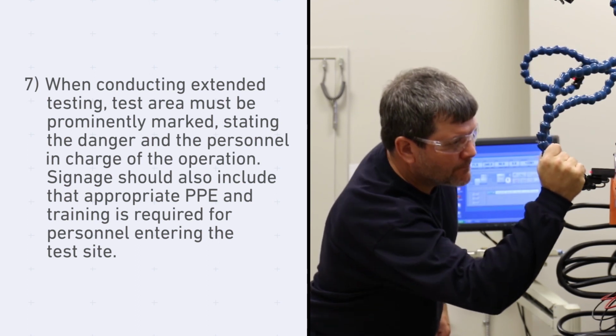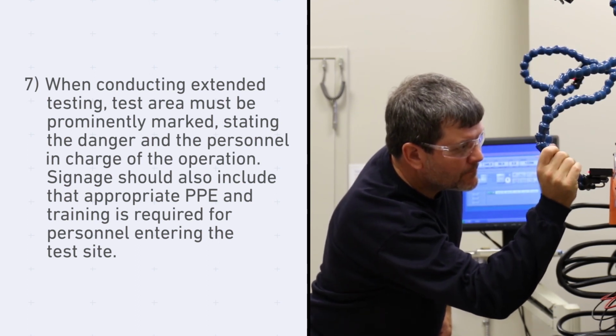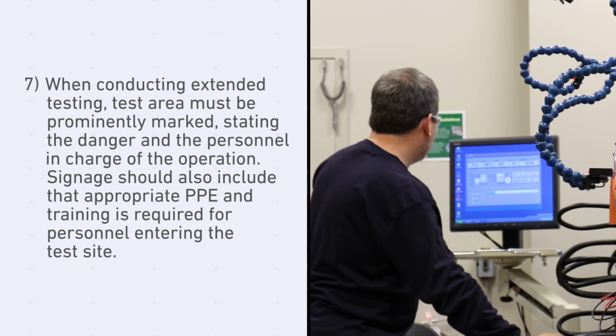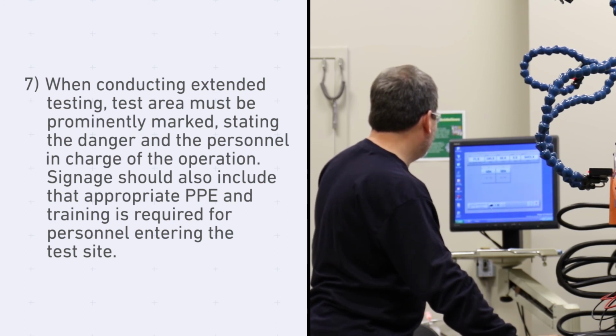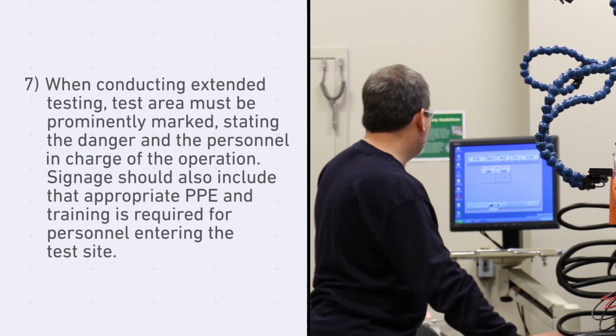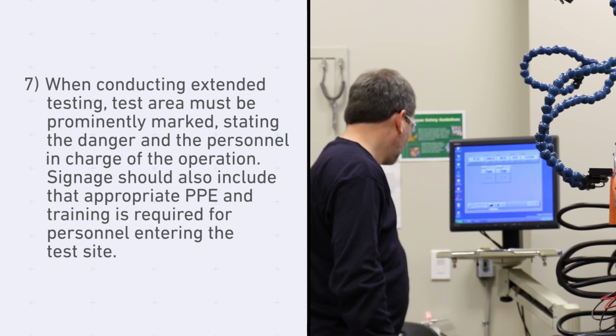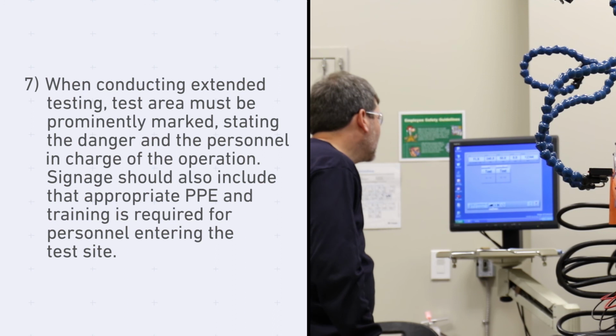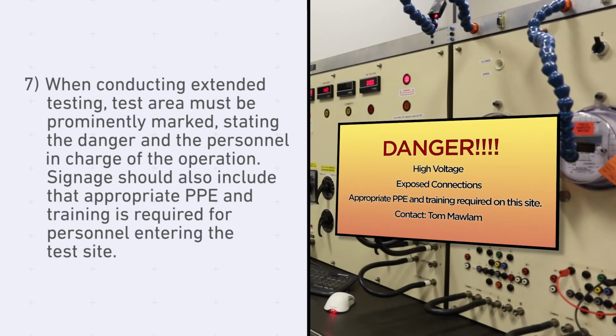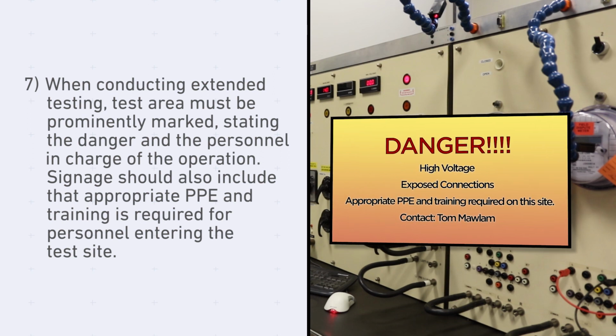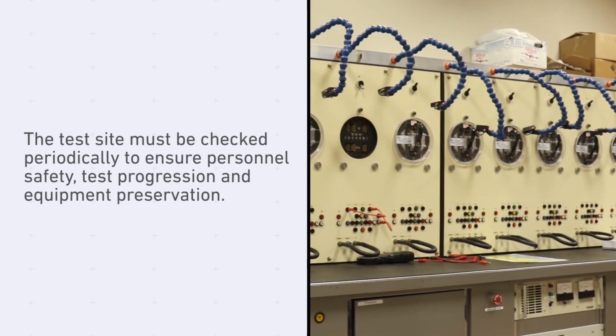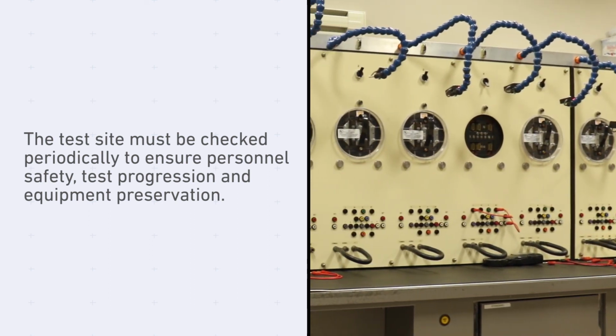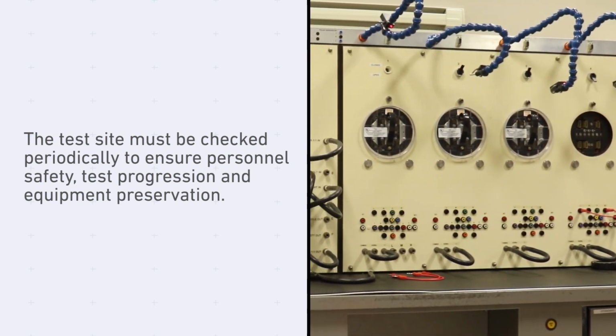7. When conducting extended testing, in which equipment will be energized for periods of time greater than normal testing, and a qualified employee will not be continuously attending, the area must be prominently marked to display the danger presented and who is in charge of the operation at hand. Entrances shall also be marked to warn anyone entering the area that appropriate PPE and training is required for entrance into the area. An employee must periodically check connected equipment for anomalies for personnel safety, test progression, and equipment preservation.